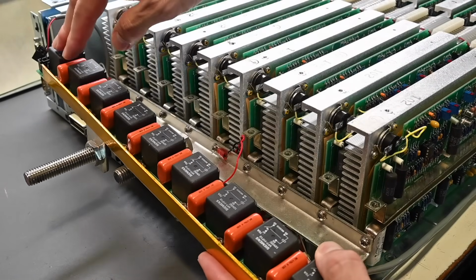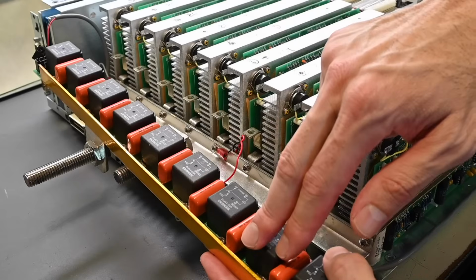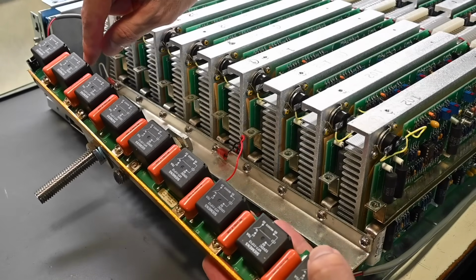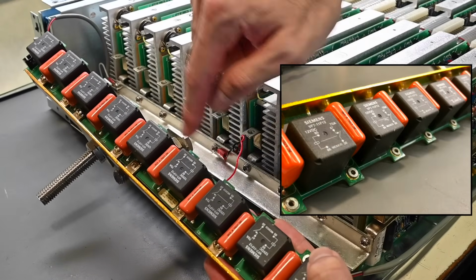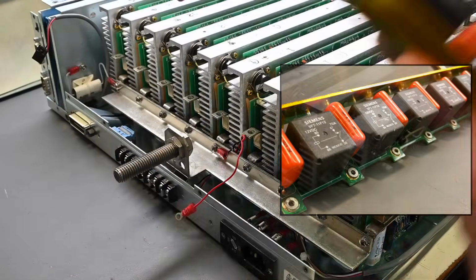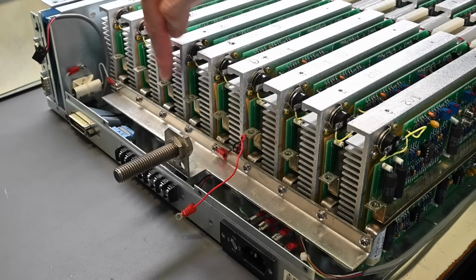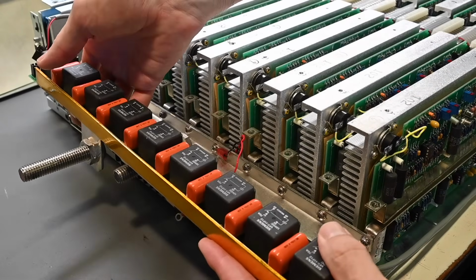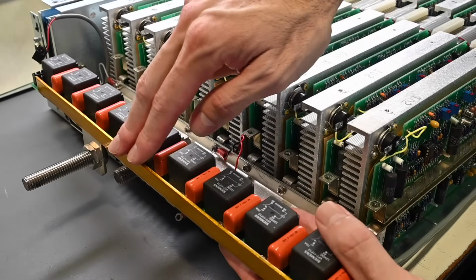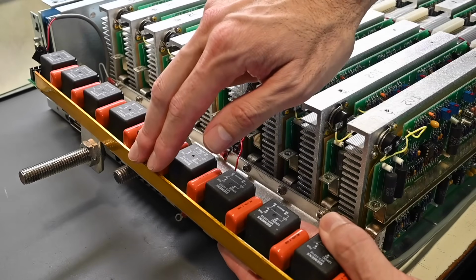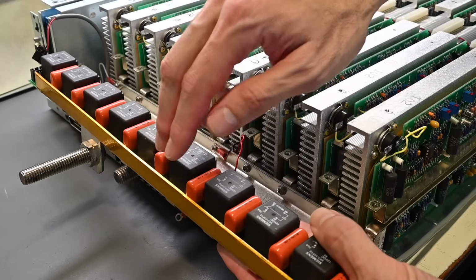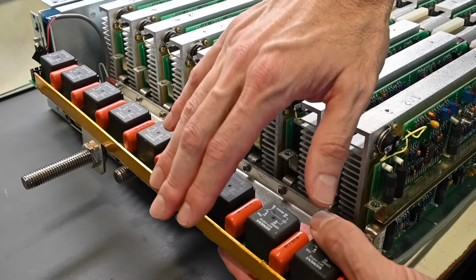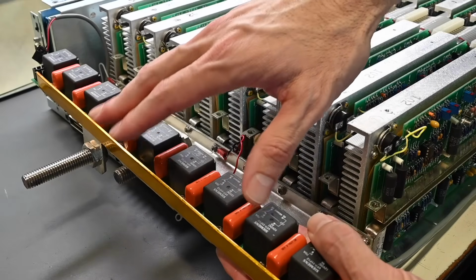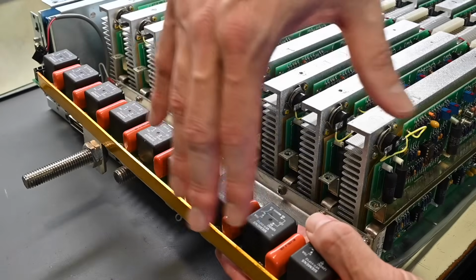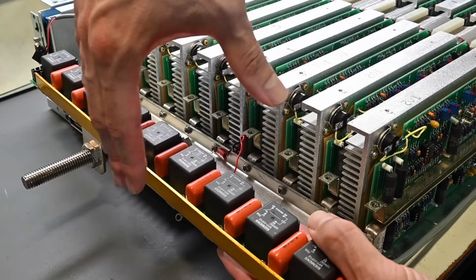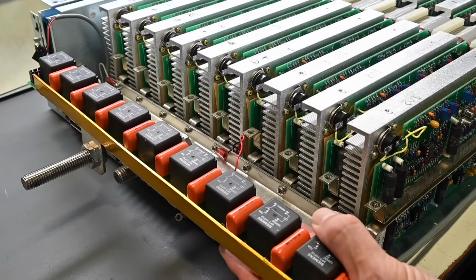This bus bar attaches to one side of each of the relay contacts. The other side of the relay contacts goes to these threaded inserts in the circuit board. So those threaded inserts are how the screws attach down through these bus bars off the modules. And if you look along this edge right here, there's this kind of a gold or amber colored tape. And the purpose of that tape is just to insulate the bus bar because they don't want to short circuit if an object would fall into the electronic load. And there's some large vents along this back edge. So this is very close to those vents. They just wanted that for protection.